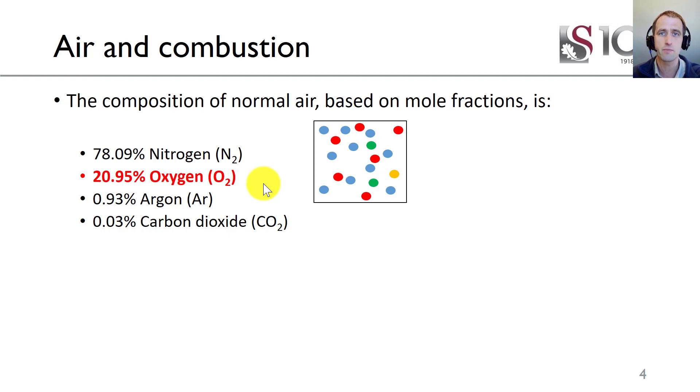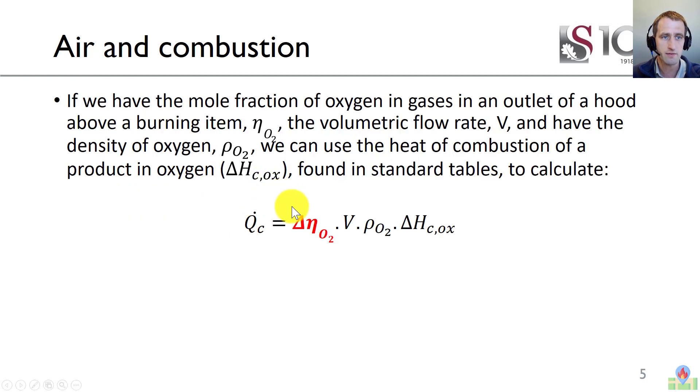That's very important because the amount of energy released per gram of oxygen consumed is relatively constant. If we have the mole fraction of oxygen in gases in an outlet of a hood above a burning item, the volumetric flow, and the density of oxygen, we can use the heat of combustion of a product in oxygen found in standard tables to calculate. So if we know the density of oxygen, volumetric flow rate, and the change in oxygen, we can get our very important heat release rate.